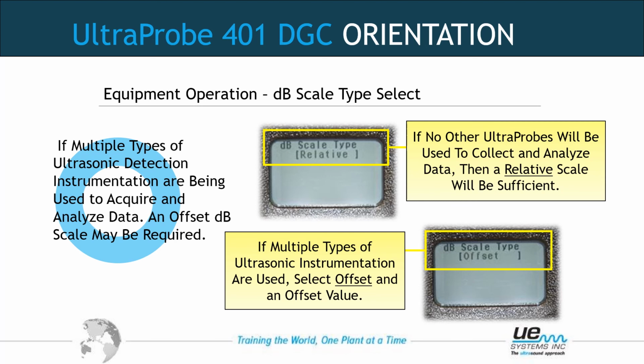So to correct this, in the Ultraprobe 401, we have an offset scale available. Normally, the dB scale is relative to UE Systems calibration. You can change that by offsetting it. So what we would do is take that 10,000 unit and the 401 unit out to a bearing. We would pick an exact test point. We would put the 10,000 on that test point. And since it's the stethoscope module, and the stethoscope module typically reads a little louder than the magnet, let's say we received 52 decibels of a reading with the 10,000. I would then take the 401 grease caddy, put the magnet in the exact location that I took the reading with the 10,000 and the stethoscope module. We see what the 401 reads.